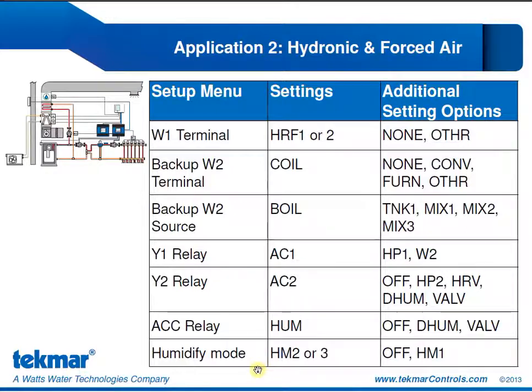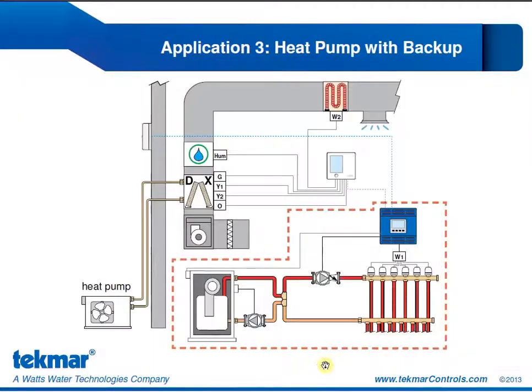Our Y1 and Y2 relays are controlling the stages of air conditioner. Accessory relay is controlling the humidifier. And because that humidifier is in the ductwork, humidify mode is 2 or 3.